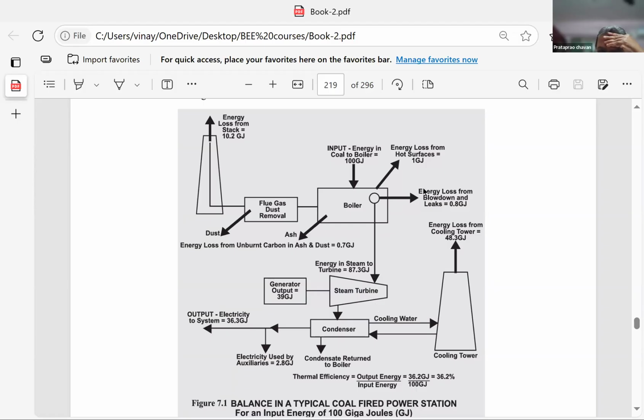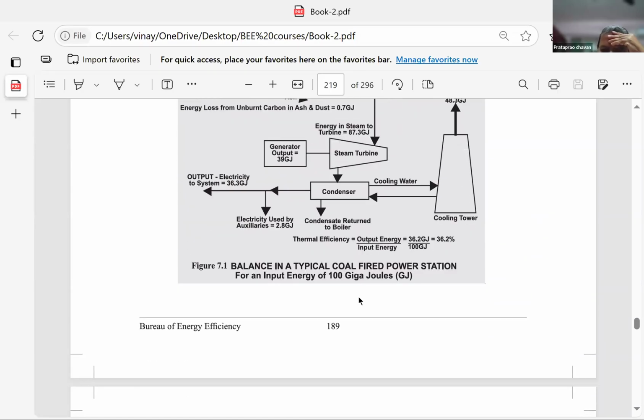Partially it is lost here, here, here. If you take the system as a whole, you will find the output of electricity here is 38, whereas the input is 100. So the base system shown here has an overall efficiency of 36%. You got the picture. Now this is the heat balance for a typical coal-fired power station. These figures may change depending on whether the equipment is old, the technology is not proper, the insulation is not good, and a lot of heat losses are going here and there, the drains and so on. So these 38 may ultimately result in 34, 35, or even 33.